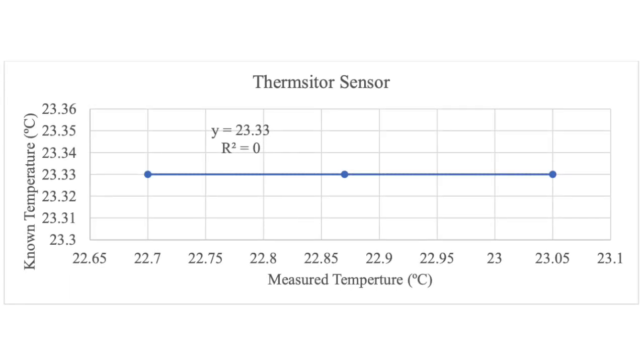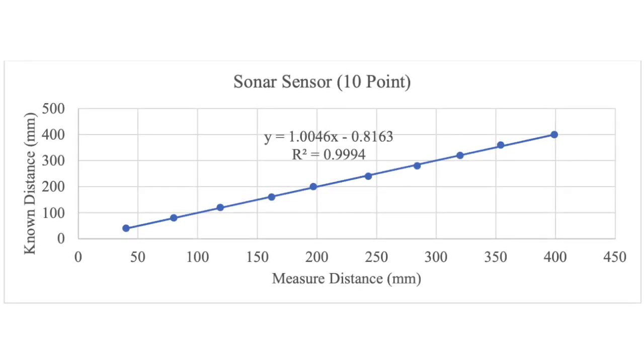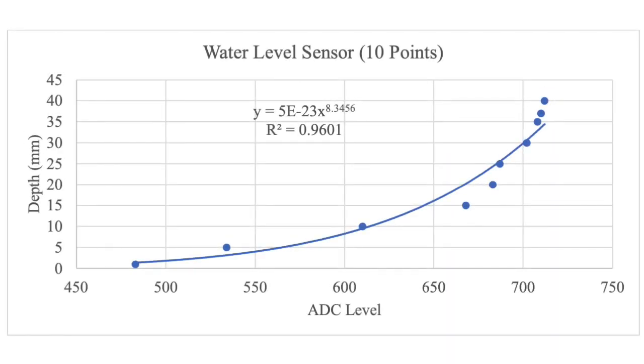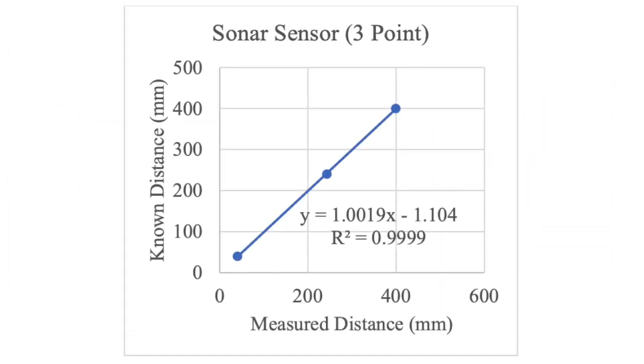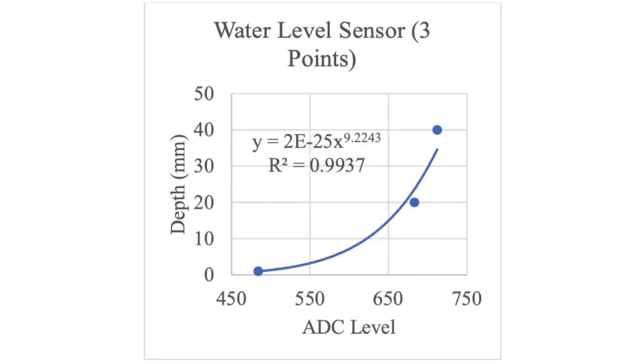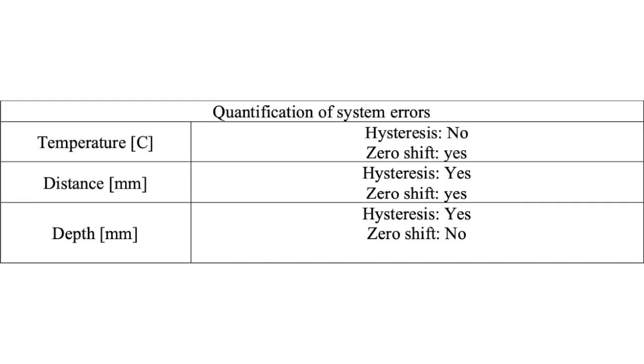The main principle learned in this project was assembling the 3 different sensors by the participants, along with collecting and calculating sets of data. The data collected determines the average trend lines for how each sensor should react, but if any data were to show a notable distance away from the natural curve, it would be flagged as an error. The 2 different types of errors found in the datasets were hysteresis and zero shift.